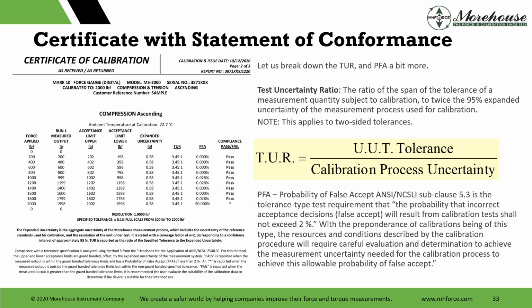And that leads, when we start talking not only about risk, into what's deemed test uncertainty ratio. This is the ratio of the span of the tolerance of the measurement quantity subject to the calibration to twice the 95% expanded uncertainty of the measurement process used for calibration. It applies for two-sided tolerances. That's one part. It's one TUR. So it's the UUT tolerance divided by the calibration process uncertainty.